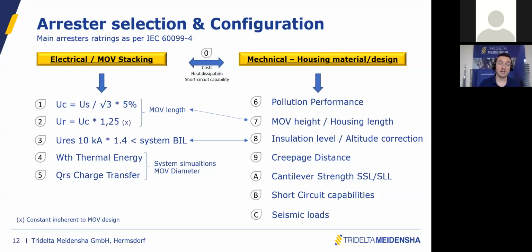Then comes the protection level, which is also called residual voltage. The lower the value, the better the protection level. What is important, and this is actually the main task of the surge arrester, is to minimize and control the stress. So you always want the residual voltage to be lower than the BIL of the system, lower than the insulation level of your equipment in the substation or in the transmission line.